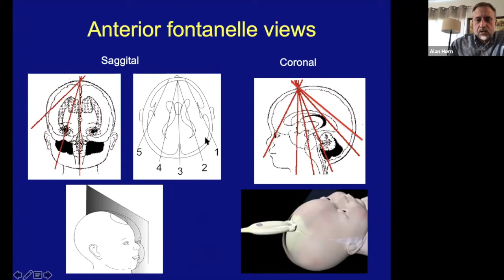Now, before we go into the details of those, a brief word about transducer choice and orientation. Micro curved array transducers are the recommended type, but you can use a phased array, which has got a flattened head if the fontanelle is too small for the curved transducer to be useful, or even if you don't have a curved transducer. It's just about resolution. Most transducers are multi-frequency, but when you set up, you will still need to choose. Now, of course, when you have a machine, there should also be an application specialist who should help you set it up. But I think it does help to have some insight into what you're setting up, particularly if you need to change the image.